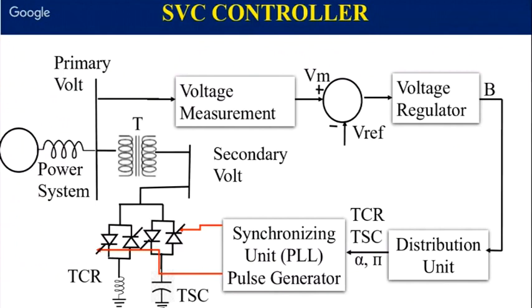Now this is the general controller used in SVC, that is, this represents the power system. It is the high voltage side, the primary side. A step down transformer is used. This is the secondary side. From the primary side, voltage measurements are done because we want to control the primary voltage basically. That is compared with the reference. The error is given to the voltage regulator.